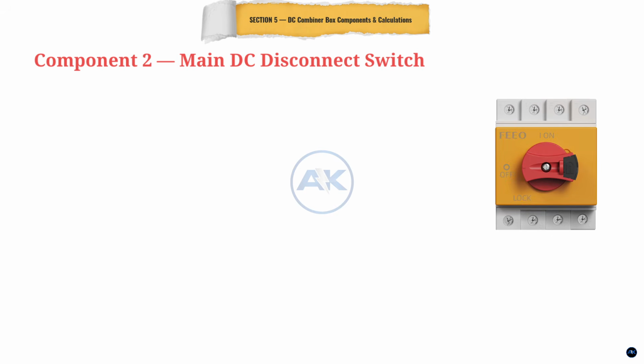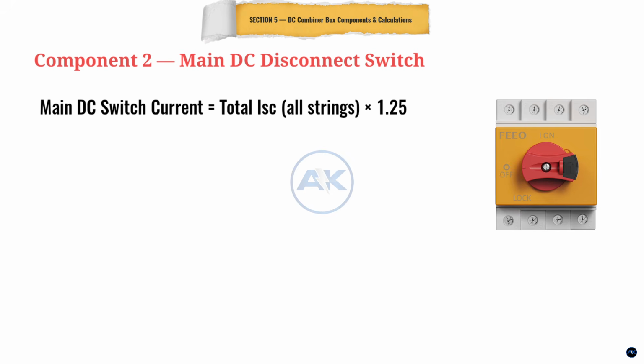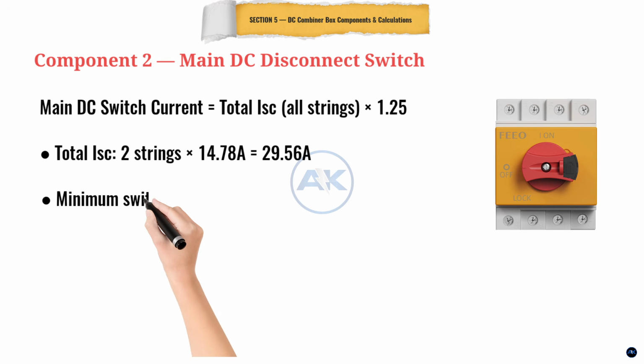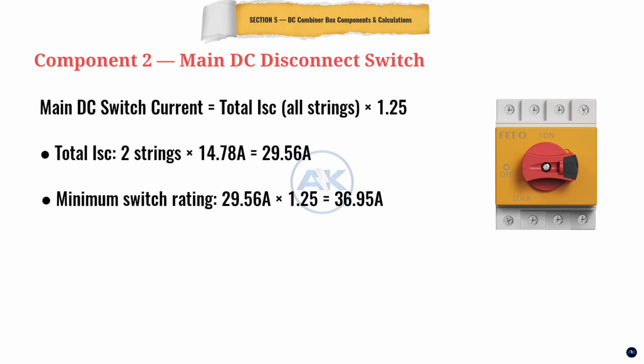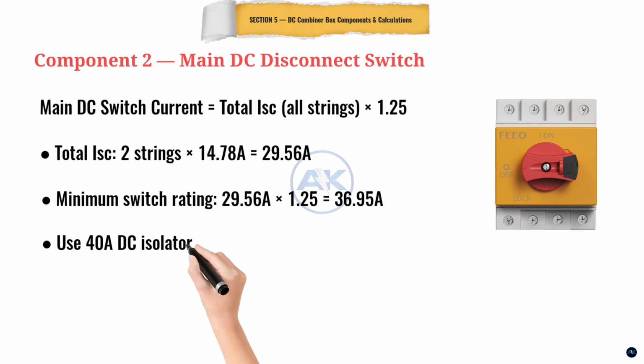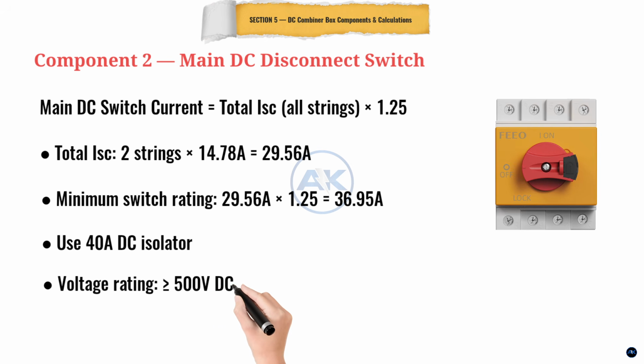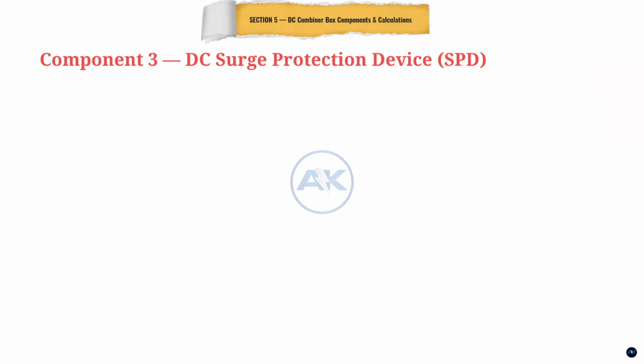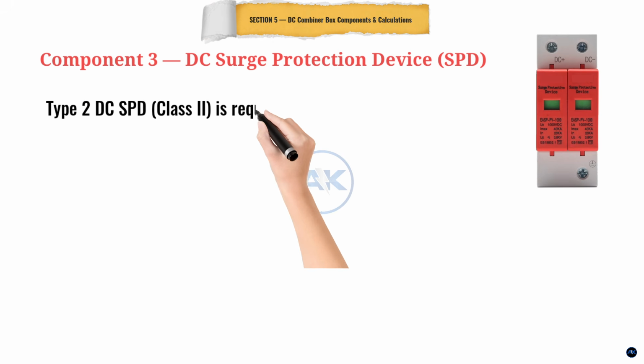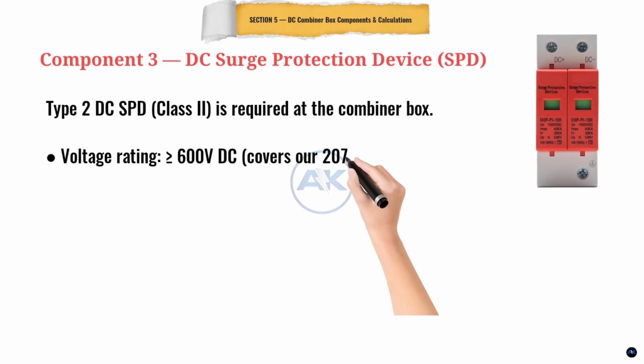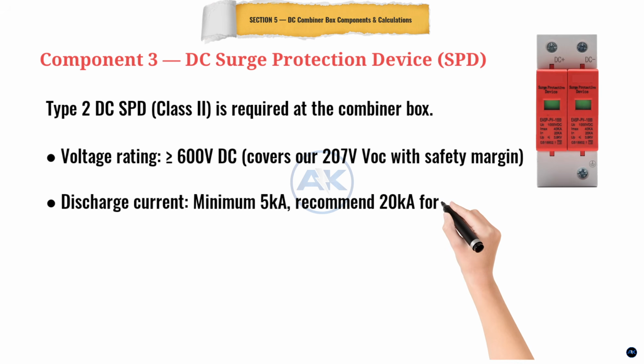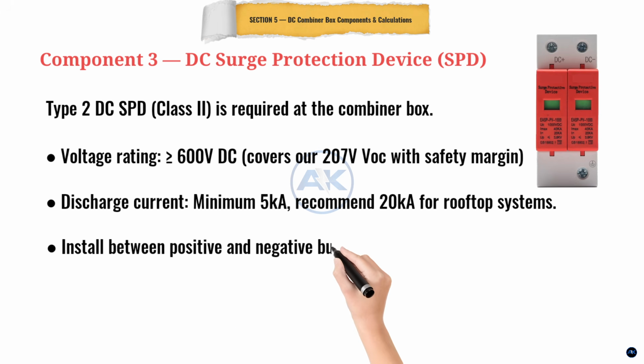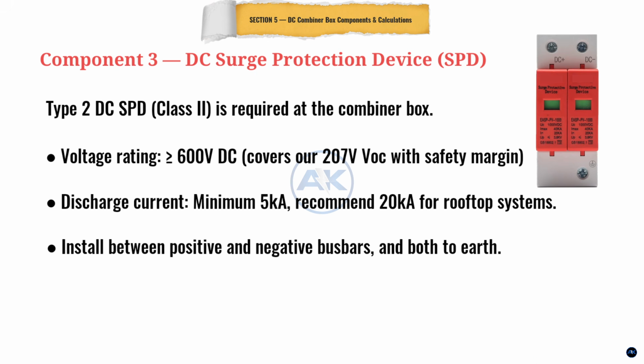Next, the main DC disconnect switch. This lets you safely isolate the entire array from the inverter. Total short circuit current from all strings, 2 strings times 14.78 amps equals 29.56 amps. Multiply by 1.25. That is 36.95 amps. We use a 40 amp DC isolator rated at 500 volts. Finally, always add a Type 2 DC surge protection device. One lightning strike without it can destroy your inverter instantly. Use one rated at 600 volts DC and at least 20 kiloamps discharge. Mount the whole assembly in an IP65 weatherproof enclosure for outdoor installation.